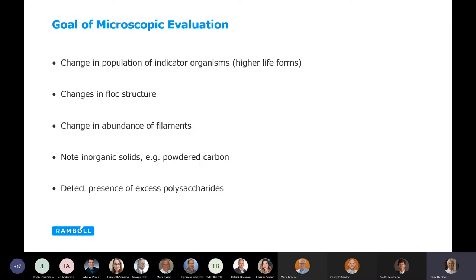The goal of a microscopic evaluation is to look at the change in population of key indicator organisms and higher life forms, change in floc structure, and the abundance of filaments — which is very important when we rely on gravity for solid separation. We can also see other things in the mass: powdered carbon, inert material, organic and inorganic matter. And we can also detect the presence of polysaccharides, which becomes very important.